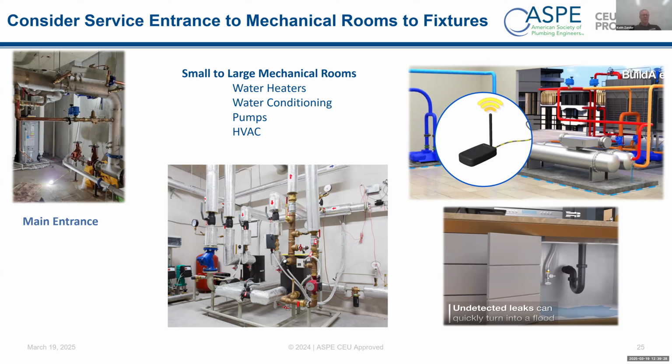But again, if you know the water's escaping out of the pipe or whatever, then you can set up the controls to where, like on that water heater right there in that room, you got rope around that water heater. So if you have real water leaking out of that system, then you can override the timer on the controls and automatically shut it off. So you don't have to wait the 30 minutes, an hour, 2 hours, 4 hours, whatever kind of setting the customer decides to put on there.